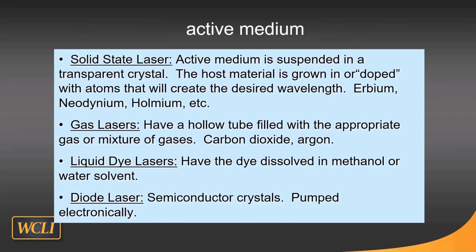Diode lasers are a different animal in that they don't use an actual crystal like the erbium-YAG and the Nd:YAG and the YSGG crystal. What they use instead is a semiconductor chip that is powered by a positive and negative electrode, and the manufacturer dials in a specific wavelength, and that's how you determine which wavelength you're using.